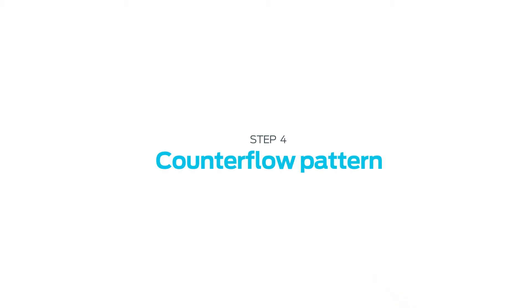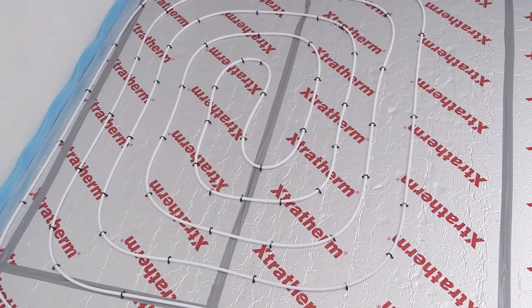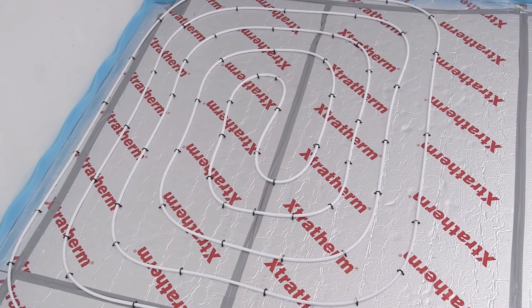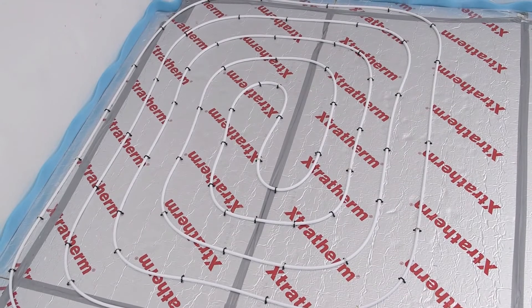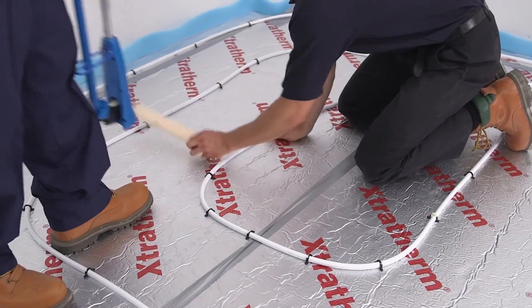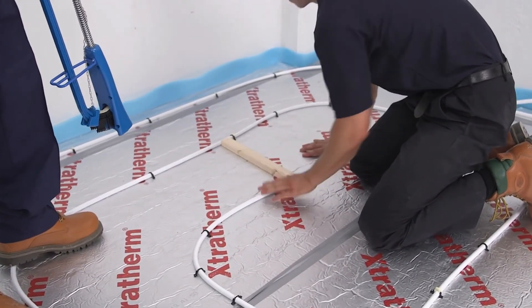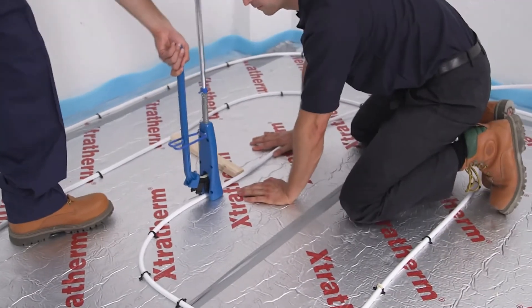Counter flow pattern. This is an example of the counter flow laying pattern. It may at first seem more complicated, but it's often easier. When installing counter flow, the pipe is laid and stapled in a spiral pattern, moving into the centre of the circuit where a double return is performed.